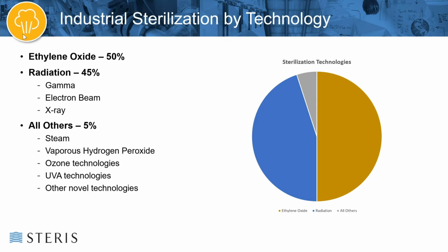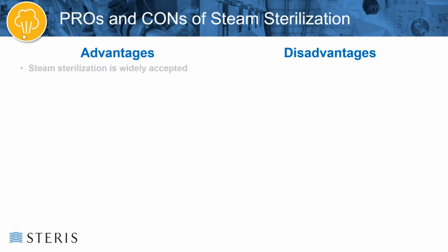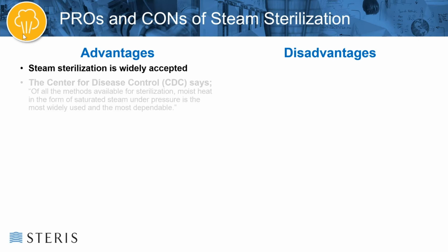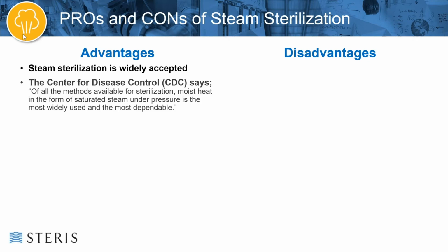So let's talk about some pros and cons of steam sterilization. There are advantages and disadvantages to this modality. One of the advantages is that steam sterilization is widely accepted globally. It's used in healthcare markets. It's used, somewhat, as we saw in that pie chart, a little bit for industrial terminal sterilization, but it is widely accepted globally. The Centers for Disease Control says that of all the methods available for sterilization, moist heat in the form of saturated steam under pressure is the most widely used and the most dependable.